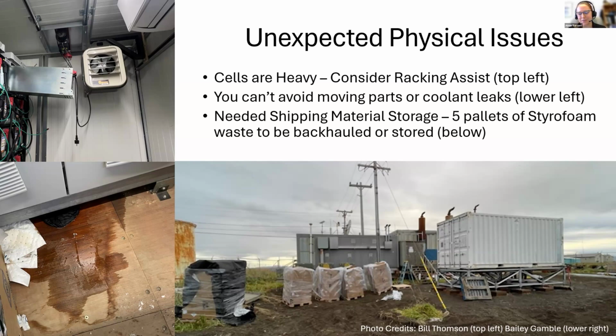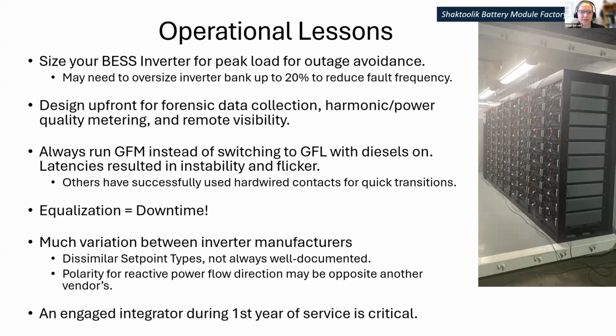Part of the appeal of these battery systems is getting away from diesels that have moving parts and a lot of maintenance. But the reality is you can't necessarily get away from operational issues like a coolant leak, which has happened as well. From electrical operation, you need to oversize your inverters and size for winter peak load to avoid outages in wintertime - even though with PV, summer is the peak generation season, you still want that battery to act as your source of redundancy.